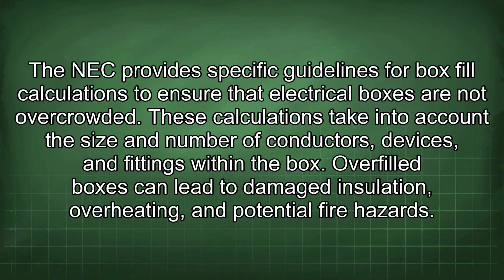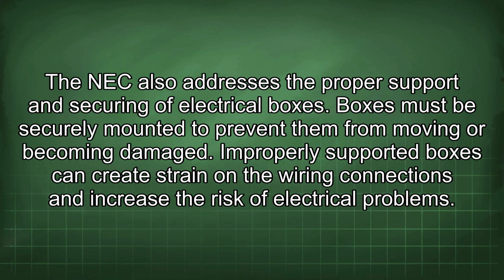The NEC provides specific guidelines for box fill calculations to ensure that electrical boxes are not overcrowded. These calculations take into account the size and number of conductors, devices, and fittings within the box. Overfilled boxes can lead to damaged insulation, overheating, and potential fire hazards. The NEC also addresses the proper support and securing of electrical boxes. Boxes must be securely mounted to prevent them from moving or becoming damaged. Improperly supported boxes can create strain on the wiring connections and increase the risk of electrical problems.